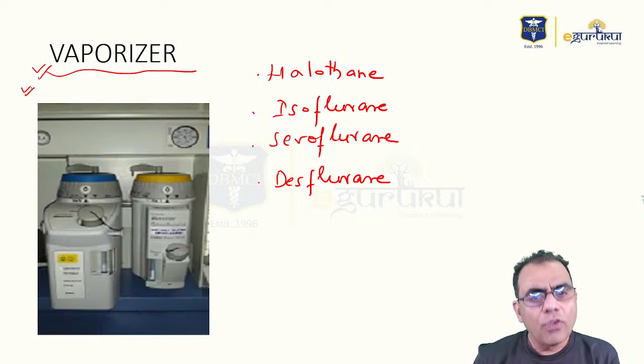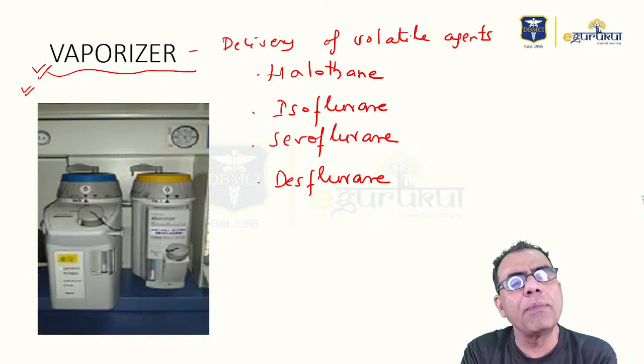which is defined for each of these vaporizers. And not only the vaporizer, actually the bottle of the vaporizer will also have the same color. For halothane, the color code is red. For isoflurane, the color code is purple, so the vaporizer as well as the bottle of isoflurane will be purple. Sevoflurane is yellow, and desflurane is blue. Now if you can see a yellow knob from a distance, which vaporizer is this? Of course, it is the sevoflurane vaporizer. A blue knob means it is the desflurane vaporizer. That is how you can identify a vaporizer from a distance.